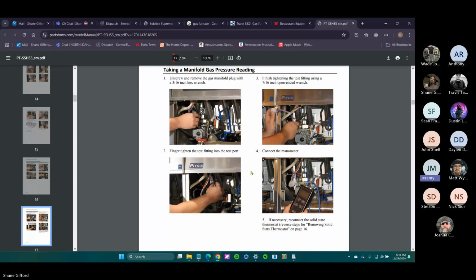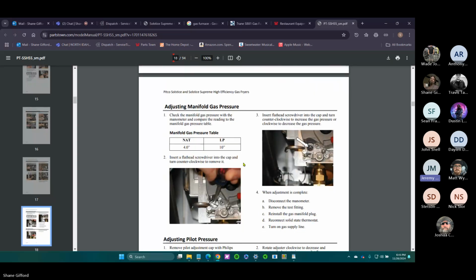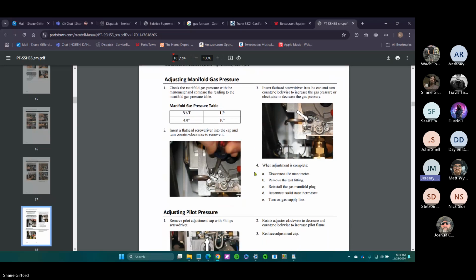Definitely confirm the solid state is bad first, because I jumped the gun when I was first dabbling a little more in hot side, and condemned a solid state at Five Guys in Pocatello and upset Jeff, because it wound up being just the $150 probe rather than the $1,000 solid state control. And we had to eat that. Unless you absolutely know for certain, like the solid state has a big hole in the middle of it because someone got mad and smashed it with a screwdriver, then on high dollar repairs like that, I urge you to call tech support and confirm your findings.